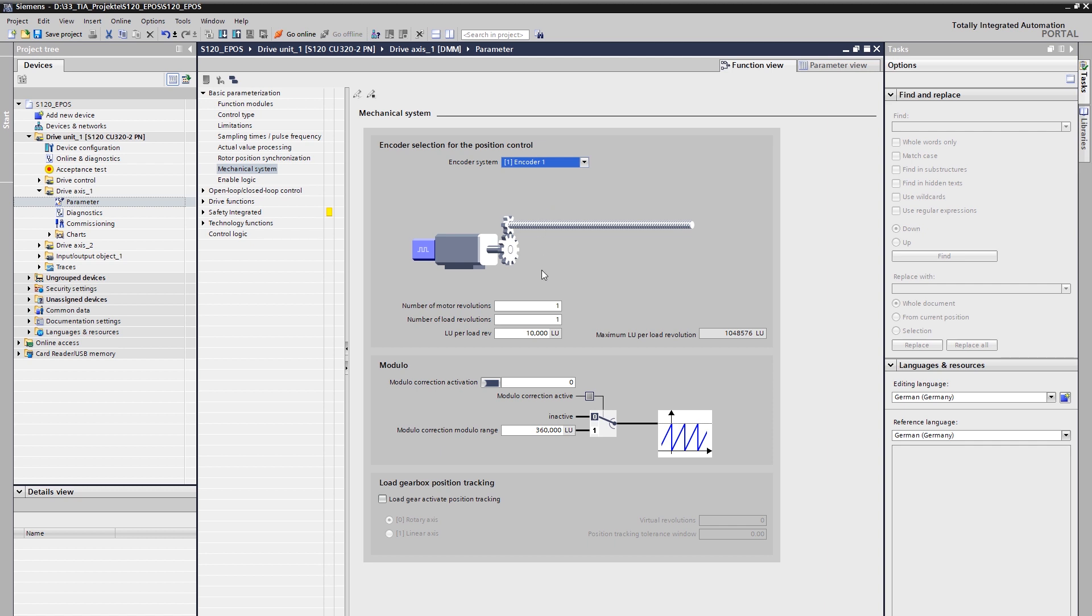The second step is to enter the transmission ratio between motor and load, if there is a mechanical gearbox. Important here, the input is made by numerator and denominator, whereby all broken ratios can be specified without rounding errors. In our example, we enter the ratio of the number of revolutions before and after the gearbox. This is only one way to describe the relationship, but it is not always as easy as in our example.